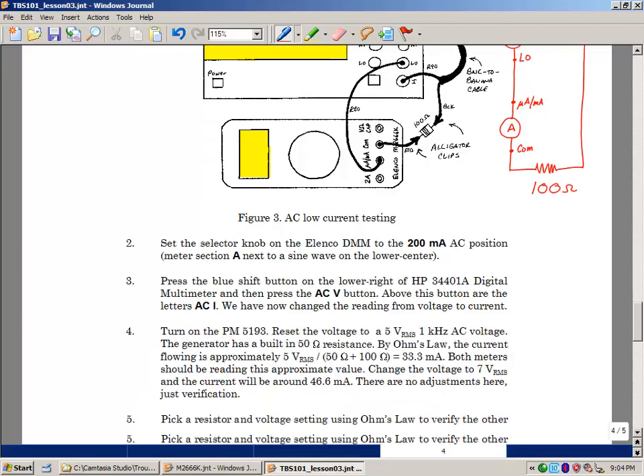Example of the calculation: I'm going to set this to 5 volts RMS, which is the unit we use for AC voltage measurements, and divide that by the total resistance in the loop here, which is 150 ohms. So we expect to see on the meter something like 33 milliamps. But the function generator isn't super accurate, so you'll be somewhere in the neighborhood of this number. All I want is to make sure both meters read the same value.